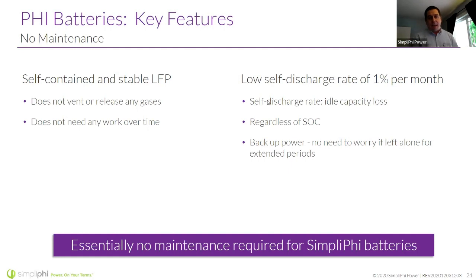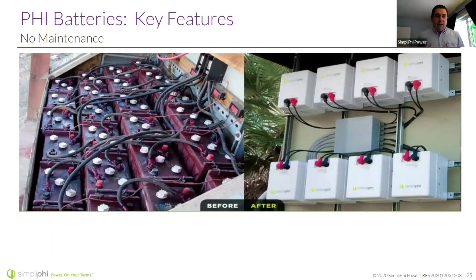Big takeaway there is that there isn't maintenance. This image is going to show you a very high maintenance bank on the left. We got a bunch of L16s. Each of those batteries has 3 caps to remove and check electrolyte and water on, a ton of battery cable, and you've got a bunch of temperature sensors. It's a mess, right? On the right, we've got a SimpliPhi bank. They've got our batteries mounted on some strut, going into a DC combiner. There's no maintenance to do here. You might refer to your electrical code and ask if you need to go back and check your torque settings periodically, but other than that, the batteries are going to be set and forget.